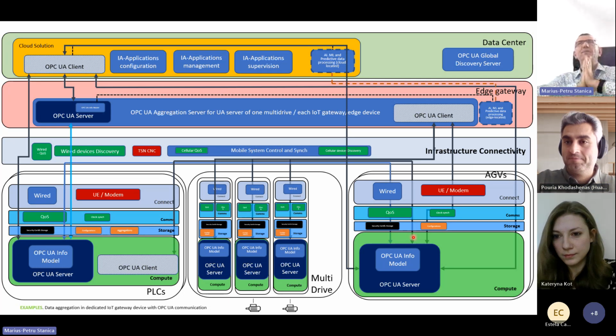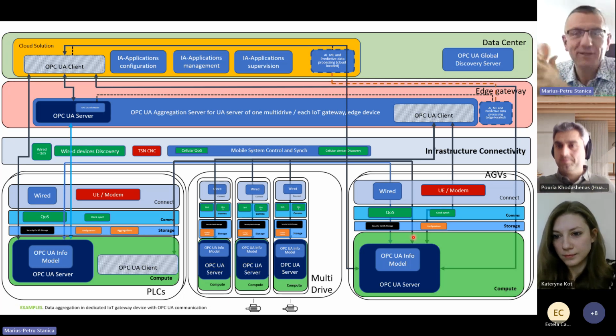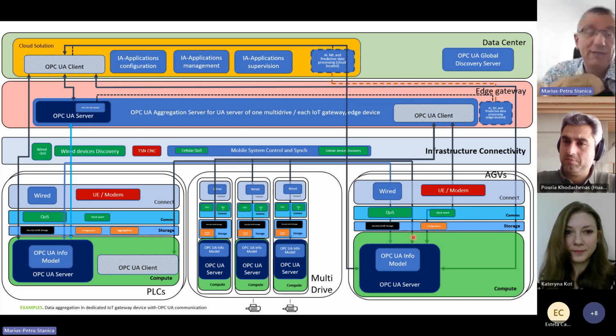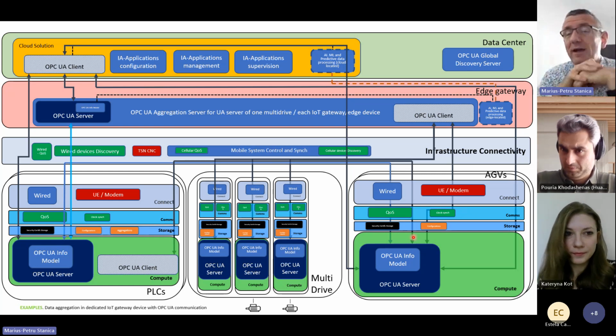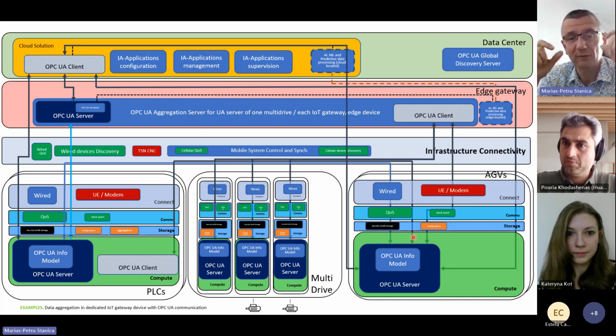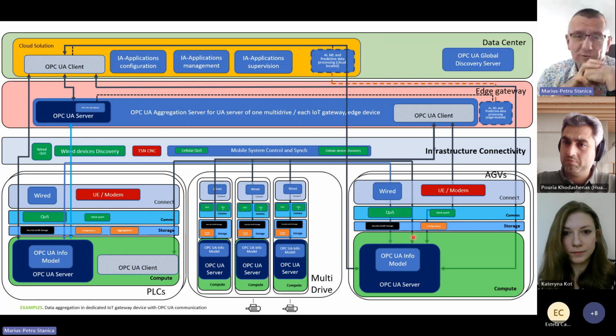First of all, you asked about real-time communication. For me, I avoid these terms because, in general, I prefer to use soft real-time or isochronous real-time. Isochronous real-time means you have a deadline of microseconds for your information to reach from one point to the other point. That means this is not for humans. This is for moving or processing something very precisely, doing motion control, doing coordinated motion.